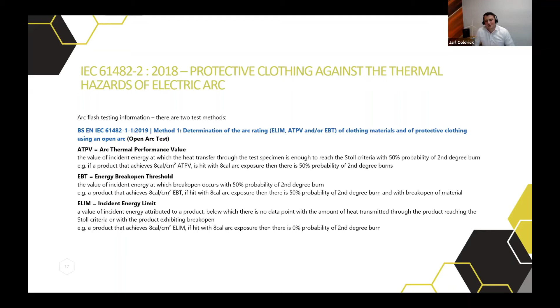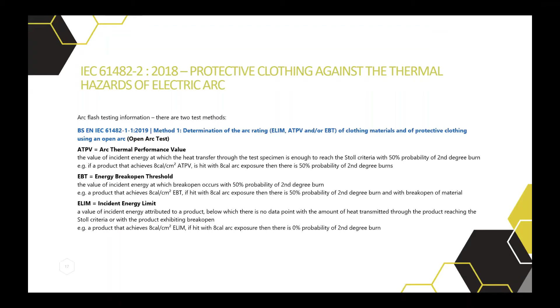So there are two test methods. You've either got the open arc test method, which gives 3 values. It used to be 2 values, only ATPV and EBT. And both those values will still give the risk of a 50% probability of second degree burns. So there's always been that element where companies haven't gone with the open arc test method for that very reason. However, ELIM has now come into place, and ELIM actually gives 0% probability of a second degree burn. So if an Arc Flash garment is 8 cal, it will actually provide 0% probability of you having that second degree burn.